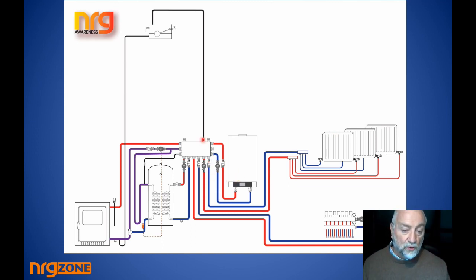There's one other thing. The open vent is taken from the exact place it should be, where there's a pipe just at the air trap where it completely vents the entire system. But the cold feed with solid fuel should always be taken as close as possible to the stove. Now, what would cause water to have a momentum to go from the cold feed to pitch out the expansion? Well, it has to be affected by a pump, unless something is boiling.